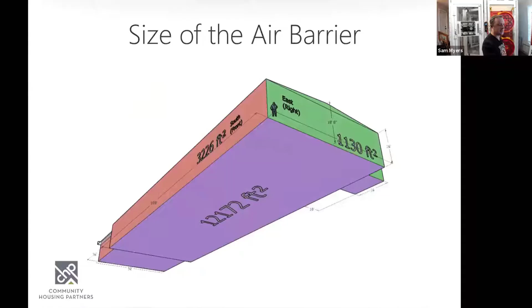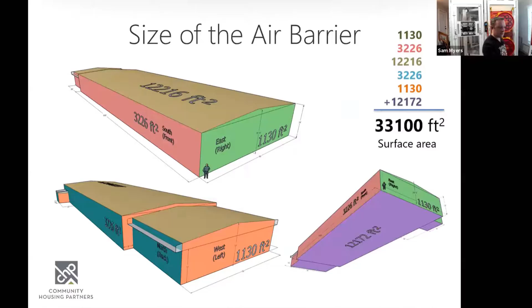Another thing about the number of fans calculator is it's just the raw math, there's no cushion built in. So if it's saying I need 4 fans to do this test, I'm probably going to get 5 or 6. It's always better to have too many than too little, because if the building is leakier than you anticipate, you still have the fan power to get a real blower door number there with good accuracy. You guys can play around with that.